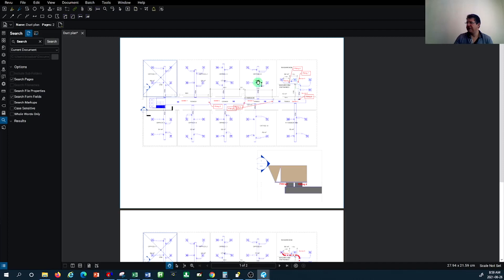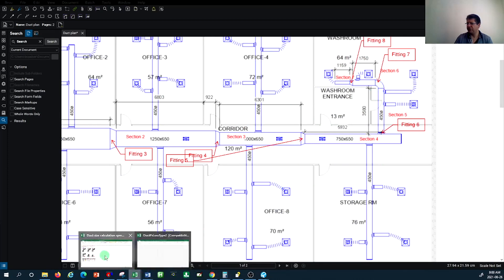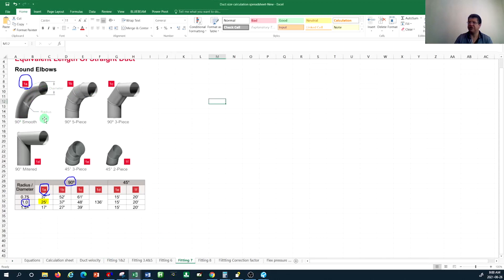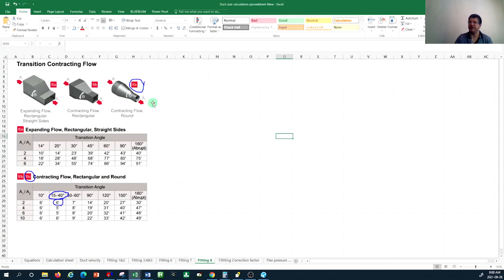Fitting seven is a round elbow. With the radius equal to the diameter of the duct, I select a ratio of 1, and because it's type 1A, the pressure drop is equivalent to 25 feet. I plug that in for fitting number seven. For fitting number eight, a round transition, the equivalent pressure drop from the table is 6 feet.